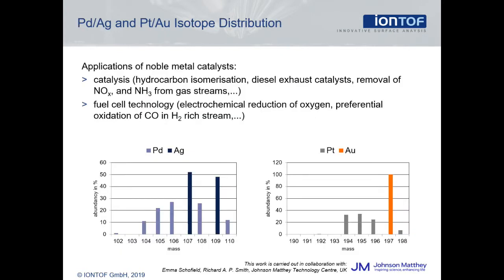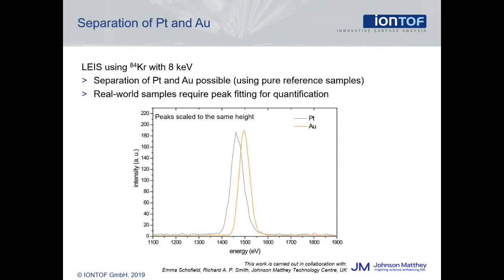One example that illustrates a classical approach to quantification is from noble metal catalysts, where elements like palladium and silver or platinum and gold are used in various catalysis applications. A challenge for LEIS is the fact that these elemental pairs have overlapping isotopes and are therefore difficult to resolve. A typical approach, besides the correlation plot method, is to measure samples with known surface concentration, for example the pure elements or their oxides. Here, using 8 kV krypton scattering and the so-called time-of-flight filter, the peaks for pure platinum and gold were measured. The peaks show a significantly different position, although due to the overlapping isotope pattern there is also a strong overlap of the peaks. This is only possible using the QTAC analyzer, which allows the operator to use heavy primary ions to improve mass resolution for heavy elements.